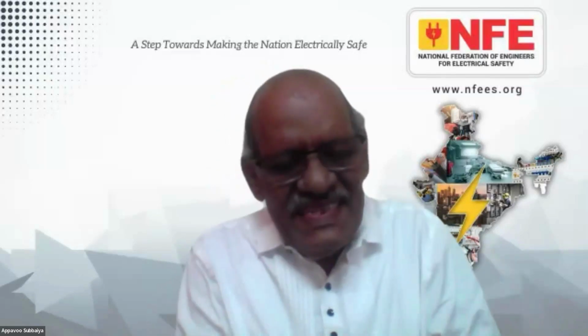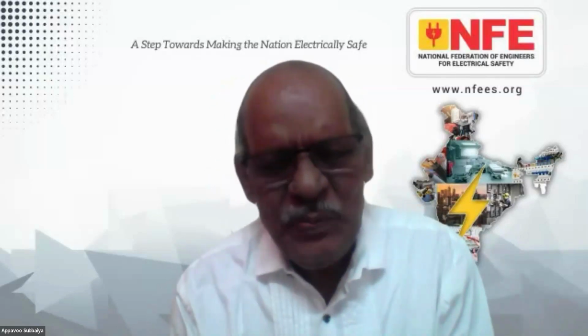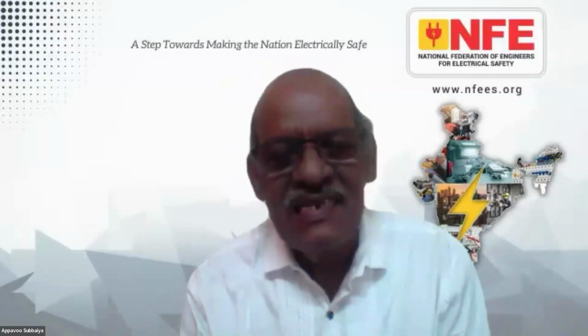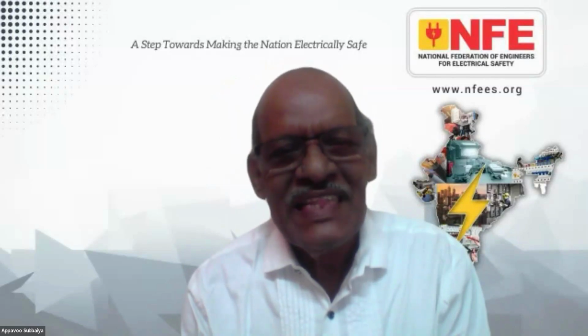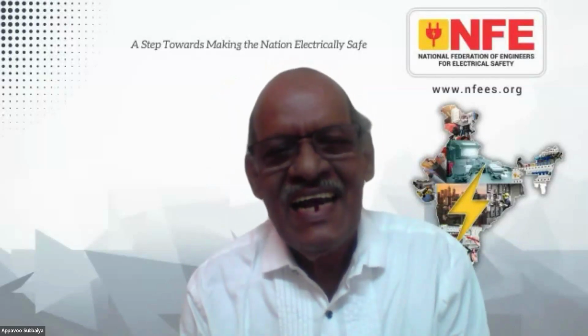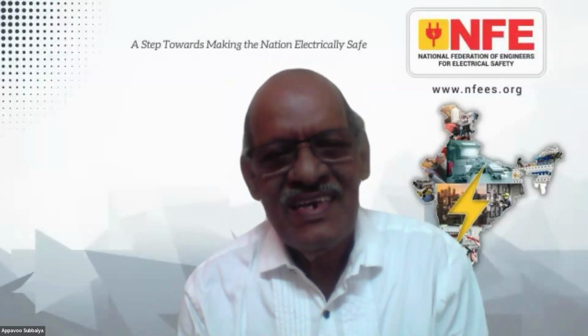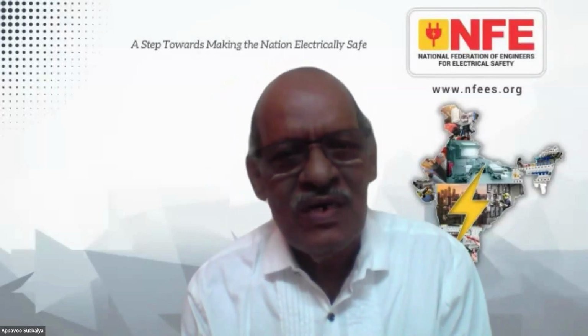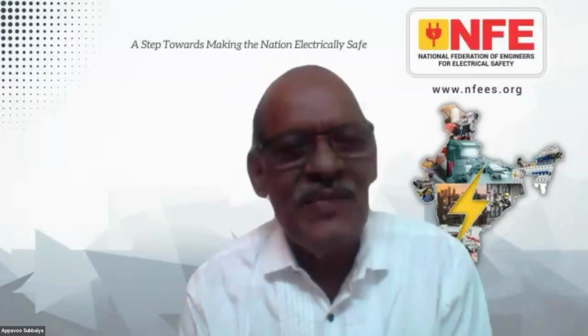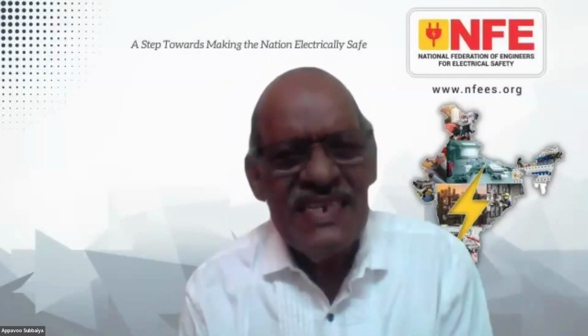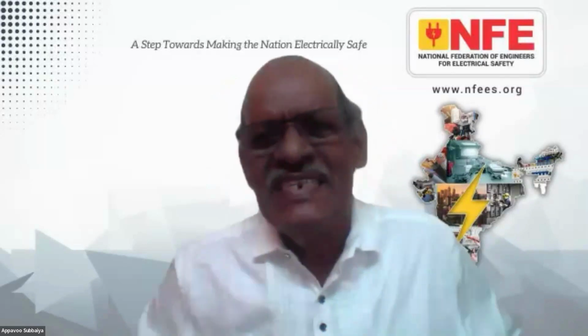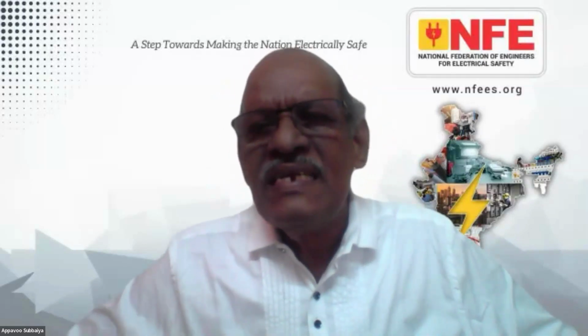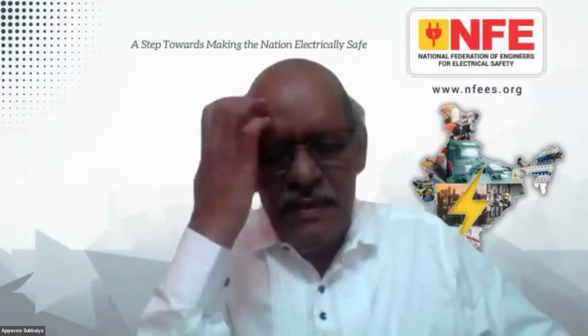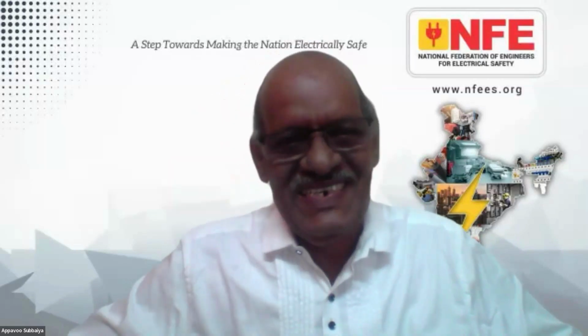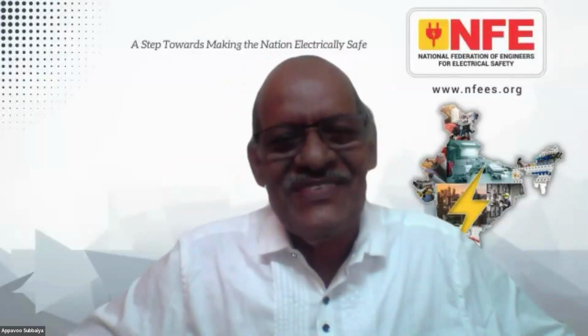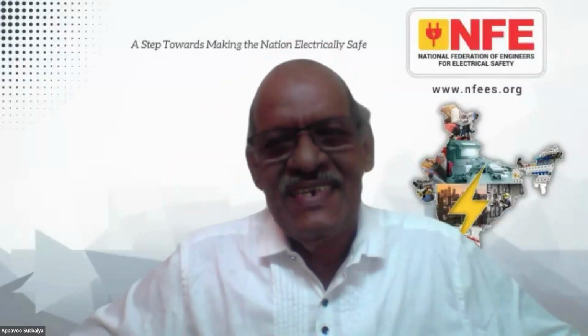Sir, this is a challenging issue. A simple 100 rupee link wire will do. They have provided an earth link after the meter board. The consumer can't provide his own earth terminal beyond the meter board. So this is in collaboration with the supplier. It's a simple thing, but it causes many hazards in our country. So there is no earth continuity from the consumer to the supplier side.